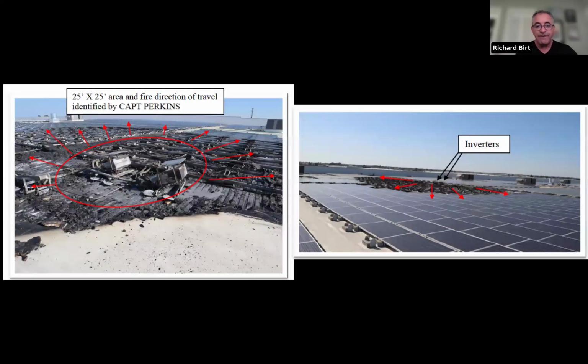But what we found from the fire inspection and the investigators was it was an arc fault at a high voltage inverter. Again, this is what I use for key guidance for the solar industry to think. Cover your real estate with solar panels. Please do that. Connect it to large storage, which is right there in the community. It's a great way of doing it. But you've got to think about all those thousands of connections and the high voltage, and having an arc fault protection system with rapid shutdown is key. Go to the next slide.